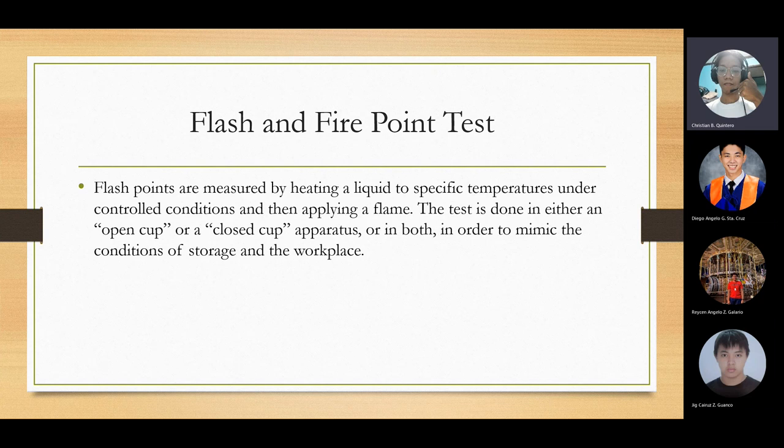Flash and fire point tests: flashpoints are measured by heating a liquid to specific temperatures under controlled conditions and then applying a flame. A test is done in either an open cup or closed cup apparatus, or both, in order to mimic the conditions of storage and the workplace. There are two types: open cup and closed cup. In open cup, the vessel containing the fuel is open to air. In closed cup, it's sealed. These two scenarios mimic different conditions, like when oil is inside an engine.